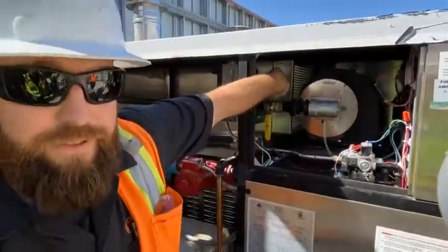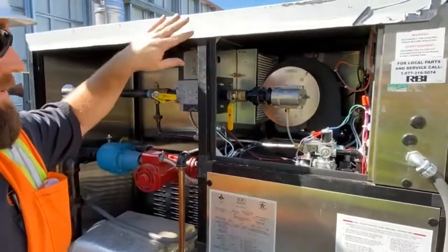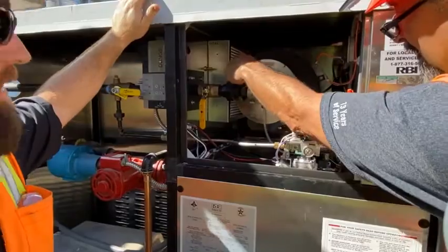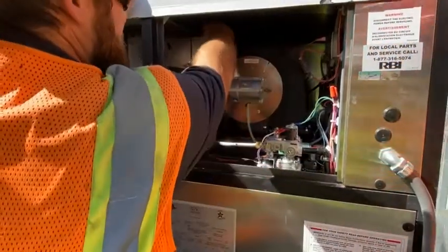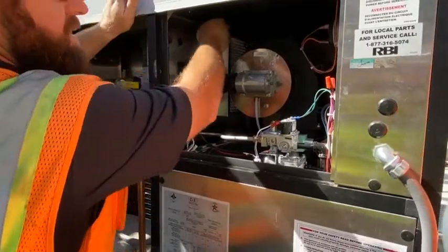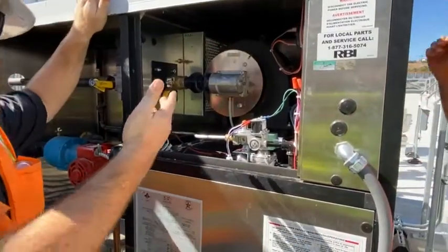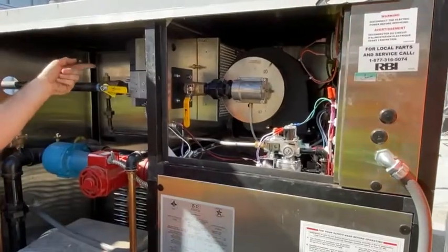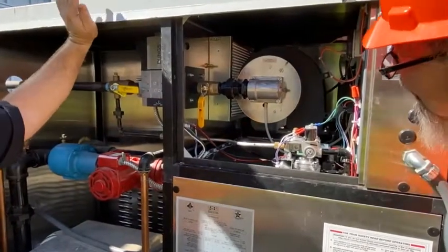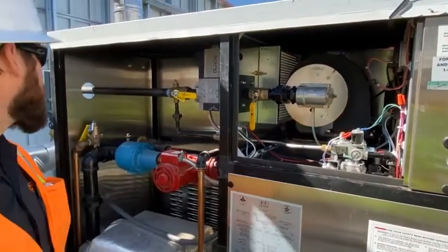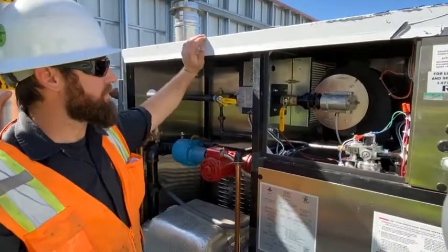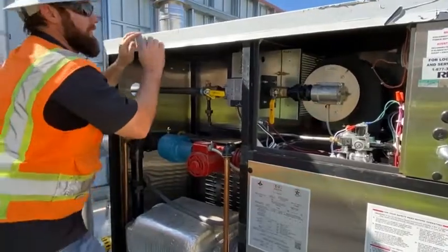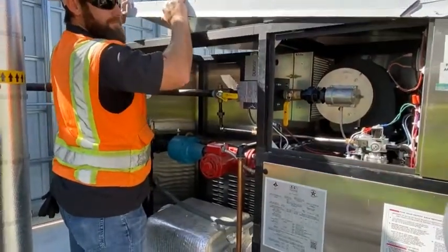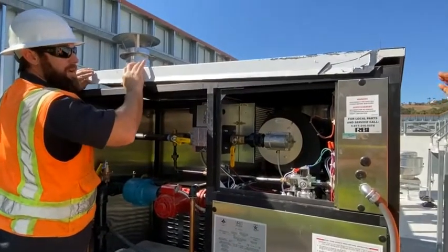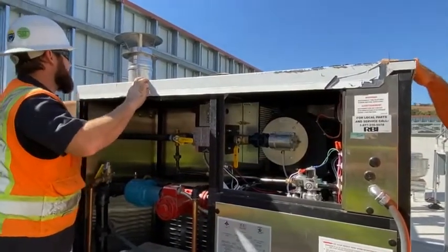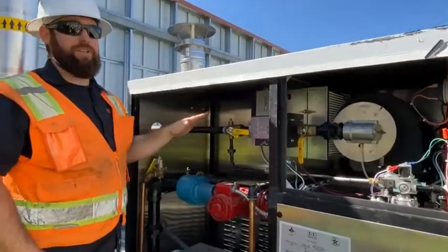So back here we've got the air filter. That's going to be your biggest maintenance thing. Right, yes. You'll be able to take it out. So you can visually inspect from the other side and this back side. But to get it out, yes, this top panel slides up and off. How does it come off? Is it screwed in? No, you just lift up. Okay. There's just a foam gasket up there. And you've got to be careful when putting it back on not to mess up that gasket. But yes, you want to make sure that filter's clean.